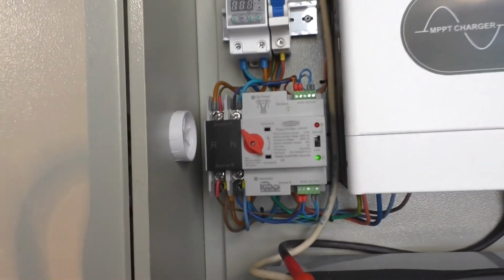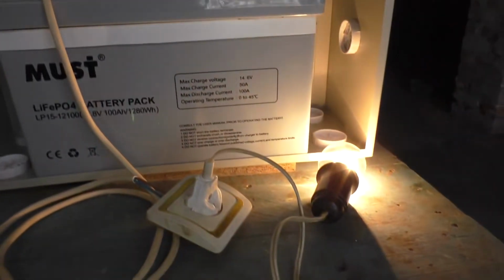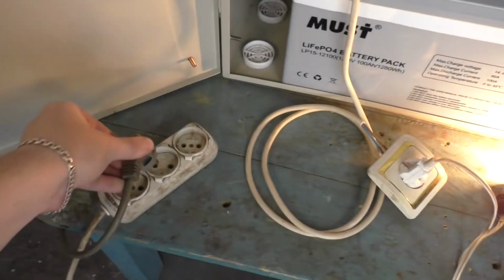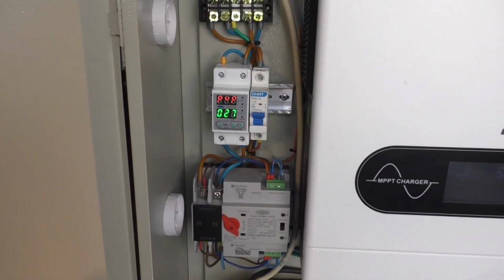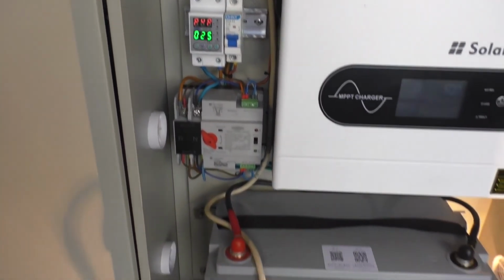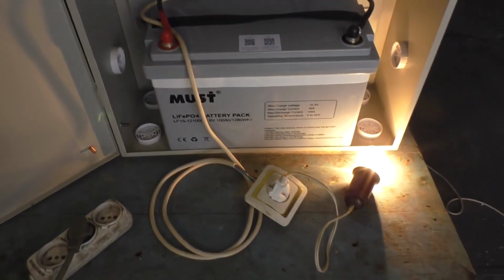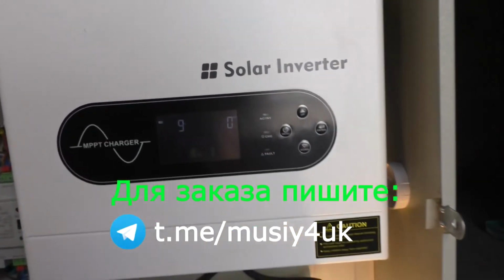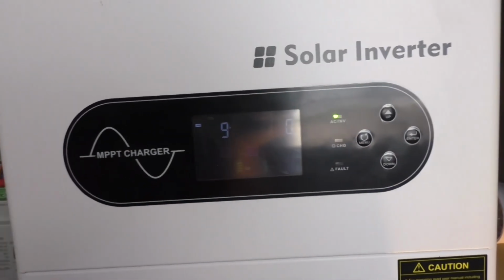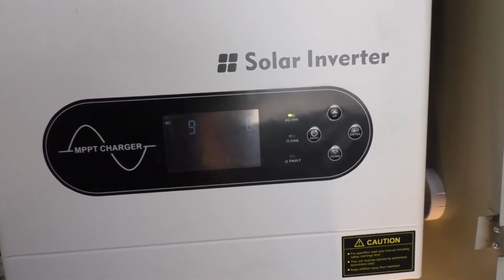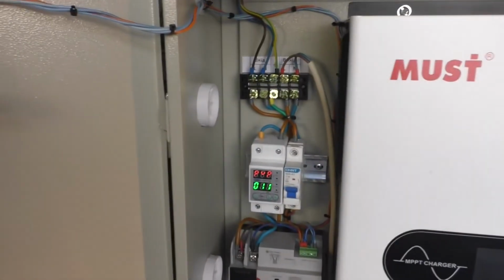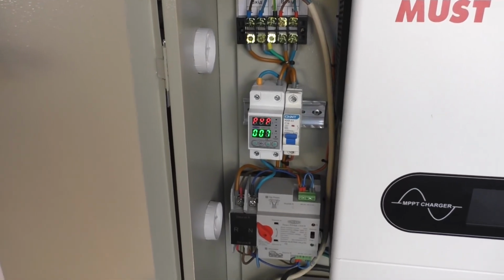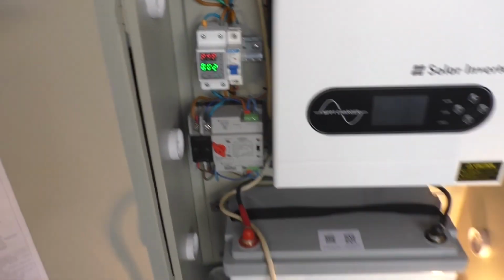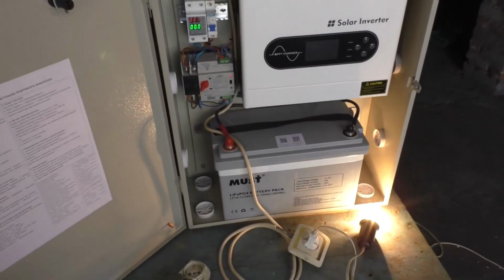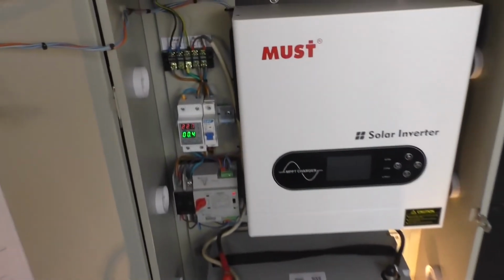The voltage relay doesn't show anything because utility power is out. Now let's plug it back in. First, the voltage relay starts up and counts down 30 seconds. You can change this time in the relay settings. Before selling, I set everything up individually for each one. The inverter screen shows the current being drawn from the battery. After 30 seconds, everything will switch back to utility power, and the inverter will charge the battery. And as you can see, everything worked perfectly.